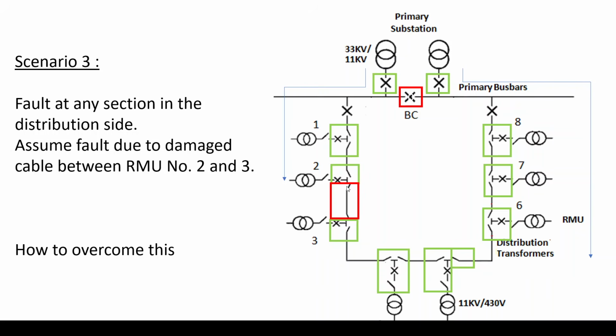So now I have opened this one, this one is closed, therefore power is coming here. This section is open, and this section is open from here. This part now is isolated, and we can work on it, whether to replace the cable or to test it or to trace the fault, do whatever we need in this section, and all my loads, all my projects, all my RMUs are having power and are not affected by this faulty section of the network.